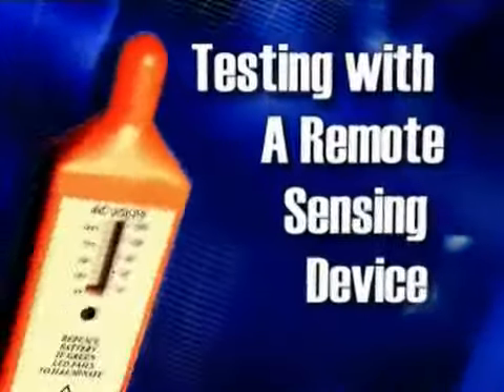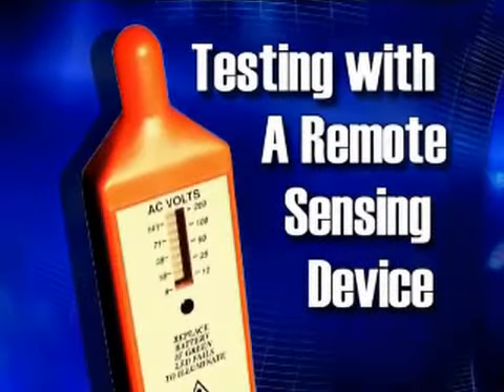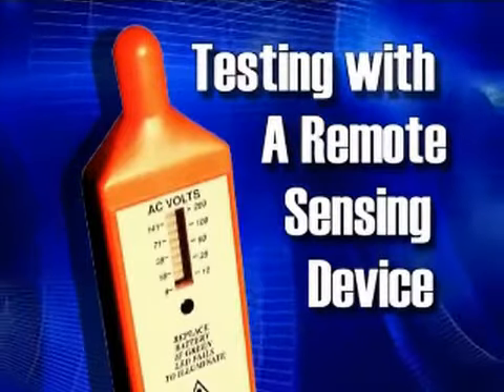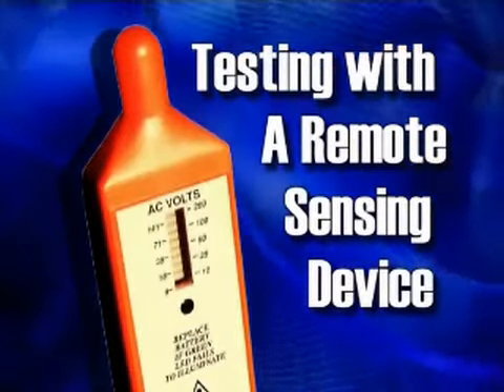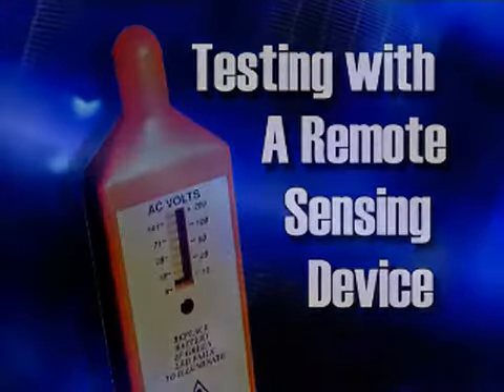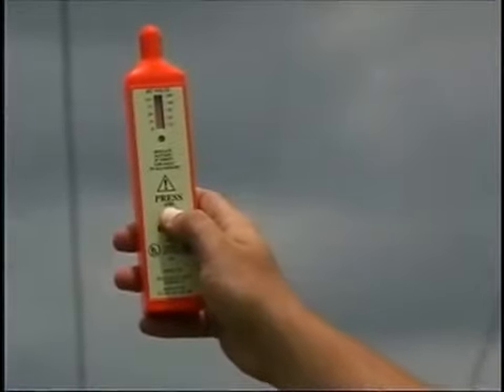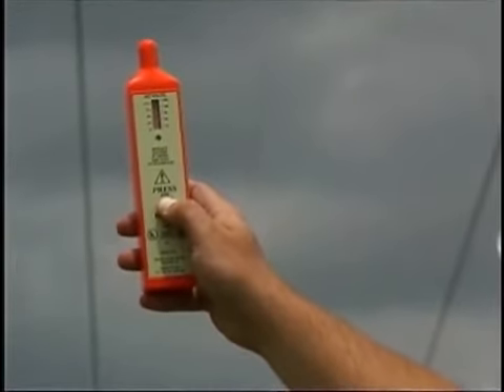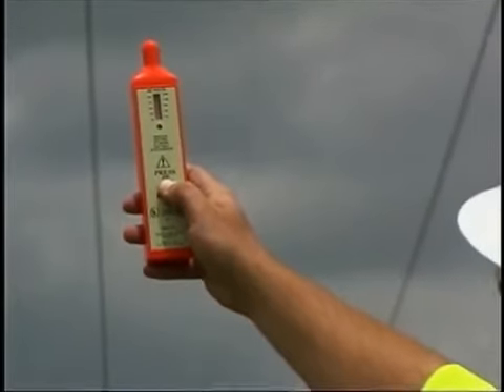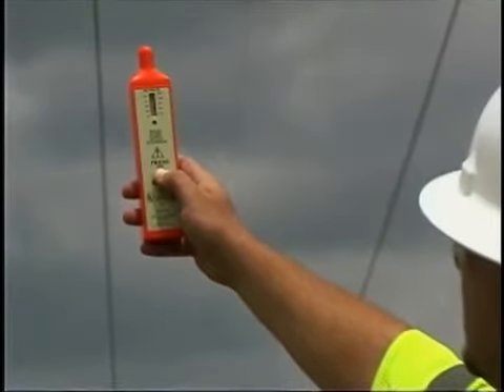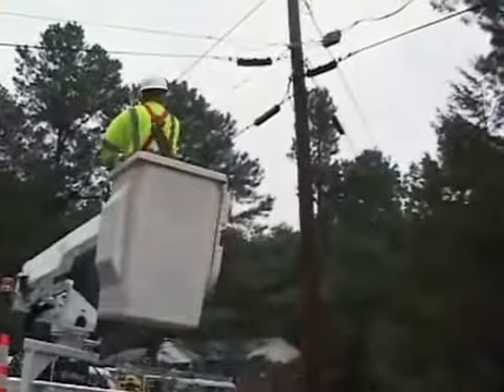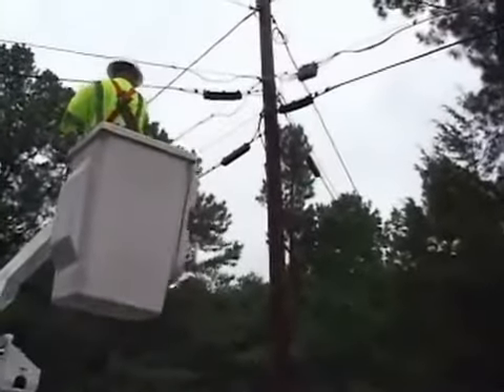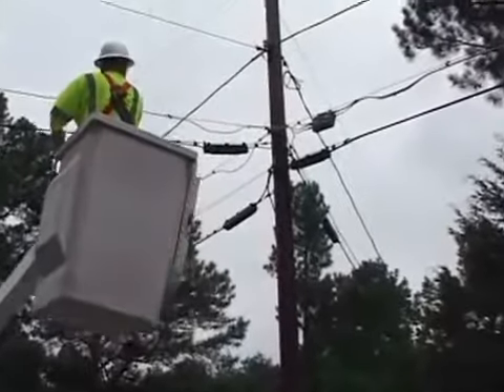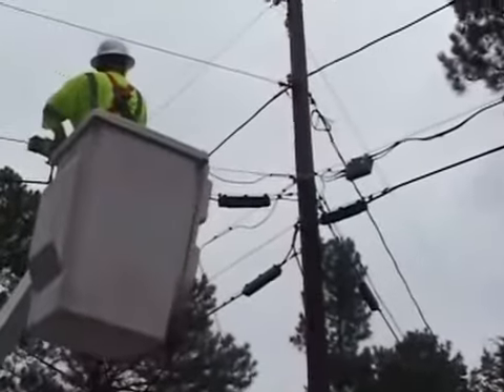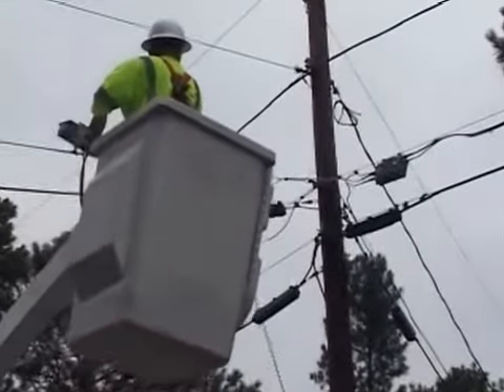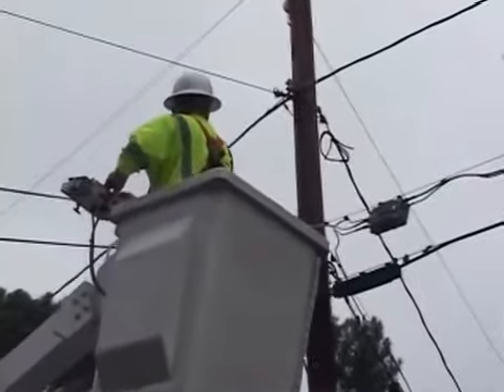Because the FVD is a remote sensing device, there are some testing situations that will produce different results. These situations require procedures that may be new to you. Users themselves may become energized due to capacitive coupling from the electric field, commonly referred to as the E field. A good example of this is in the vicinity of power transmission lines or under power distribution lines. This may cause the FVD to indicate a hazardous condition when it does not exist.